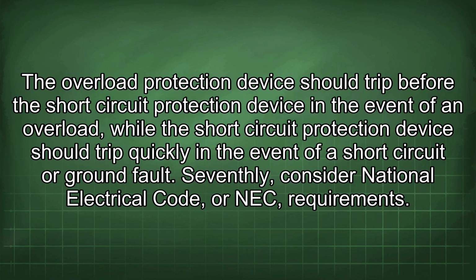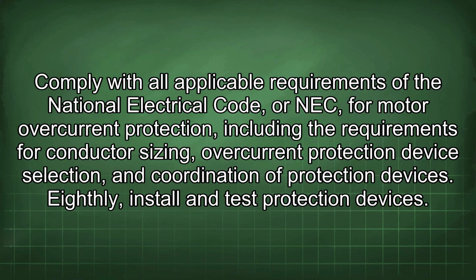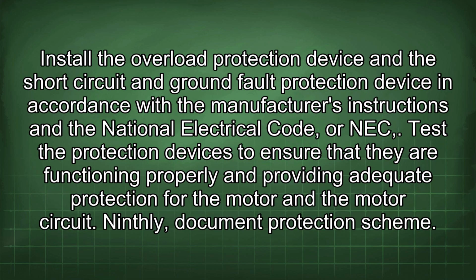Seventhly, consider National Electrical Code, or NEC, requirements. Comply with all applicable requirements of the National Electrical Code, or NEC, for motor overcurrent protection, including the requirements for conductor sizing, overcurrent protection device selection, and coordination of protection devices. Eighthly, install and test protection devices. Install the overload protection device and the short circuit and ground fault protection device in accordance with the manufacturer's instructions and the National Electrical Code, or NEC.